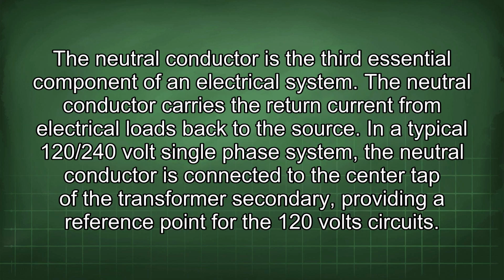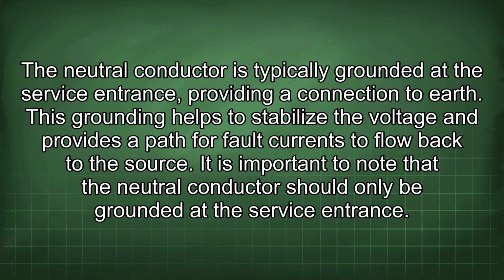The neutral conductor is the third essential component of an electrical system. The neutral conductor carries the return current from electrical loads back to the source. In a typical 120/240 volt single-phase system, the neutral conductor is connected to the center tap of the transformer secondary, providing a reference point for the 120 volt circuits. The neutral conductor is typically grounded at the service entrance, providing a connection to earth. This grounding helps to stabilize the voltage and provides a path for fault currents to flow back to the source.